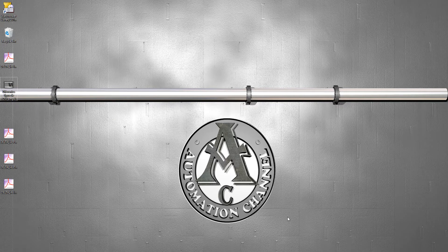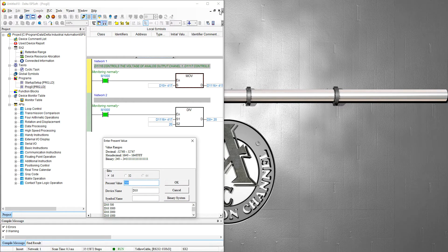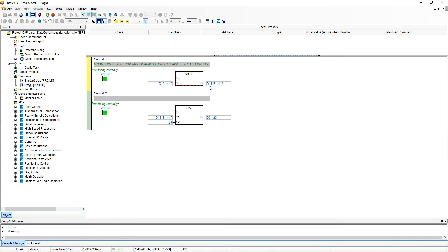First of all let's open ISPSoft. If you want to change the voltage output of channel 1, you just need to modify D1116. The range for the voltage output is 0 to 10 volts, and the range of the value you can give to D1116 is between 0 and 2000. If you give a value of 2000, the output voltage on channel 0 will be 10 volts. If you give D1116 a value of 1000, the output voltage will be 5 volts, so the range is between 0 and 2000.